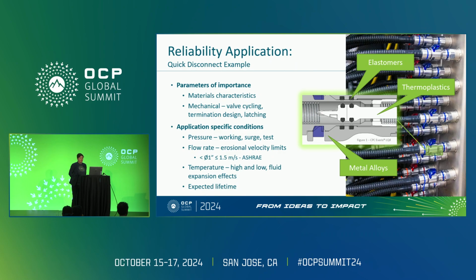Okay, isolating the QD, again, as an example of a key component within the TCS, reliability really comes down to two key elements: material characteristics, and then mechanical function and stress over time. On top of that, to effectively deploy a QD, we want to account for materials and stresses that might be present during the actual operation. So for the purposes of this conversation, breaking the QD down by material, metal alloys, engineered thermoplastics, elastomers, and then characterizing the performance of those materials in the system, we can set a foundation for a broader reliability model that can extend to other components and products that are in that ecosystem.